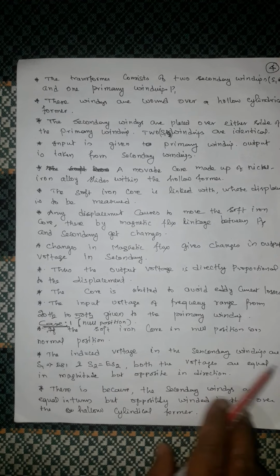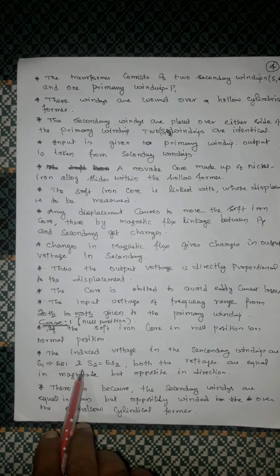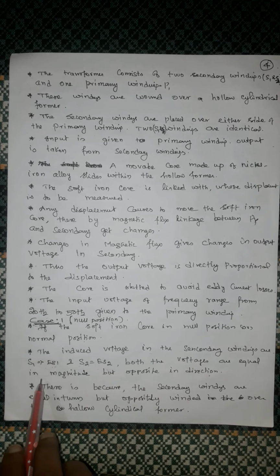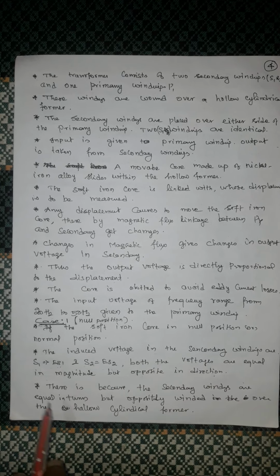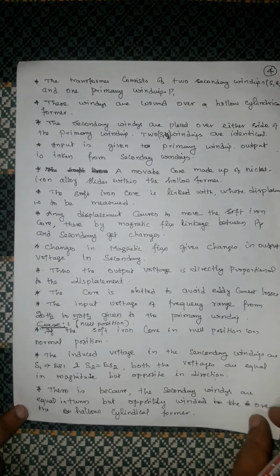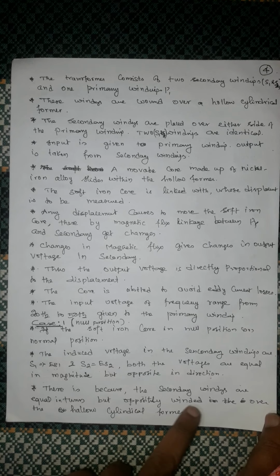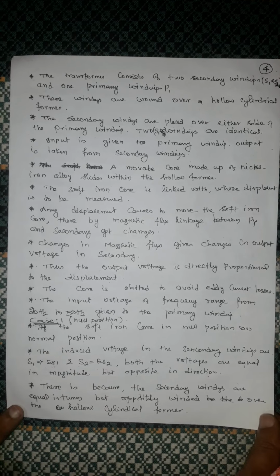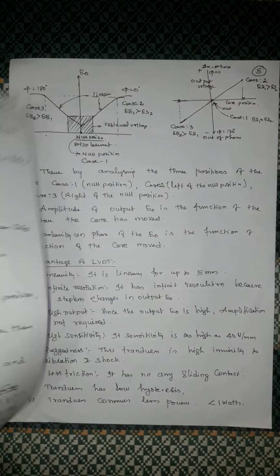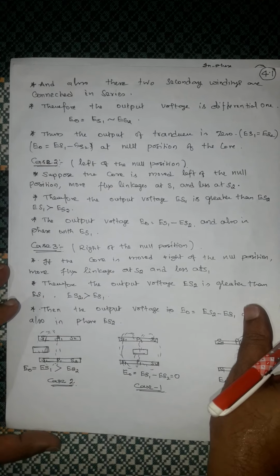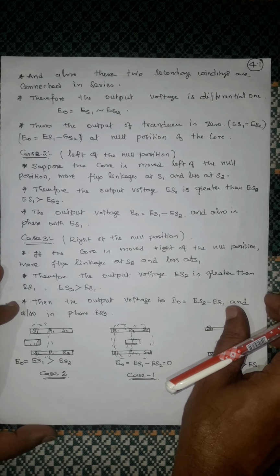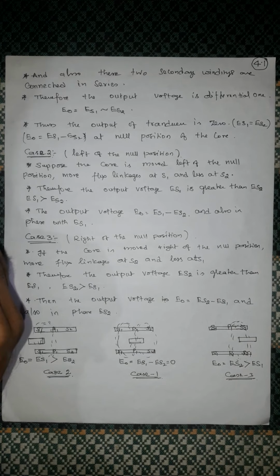The induced voltages in the secondary windings, S1 equal to ES1 and S2 equal to ES2, are equal in magnitude but opposite in direction. This is because the secondary windings have equal turns but are wound oppositely over the hollow cylindrical former, and these two secondary windings are connected in series.